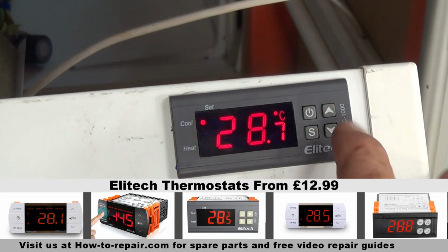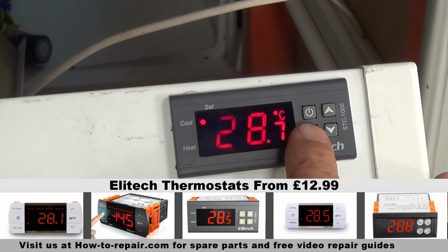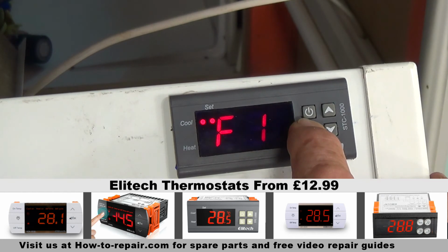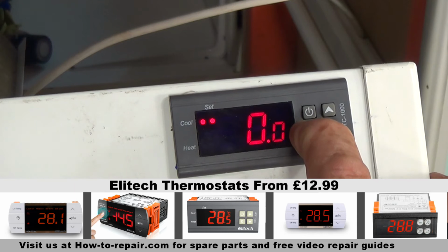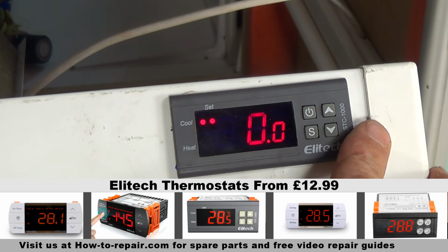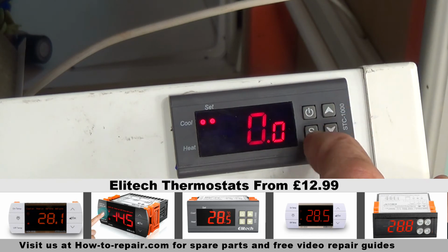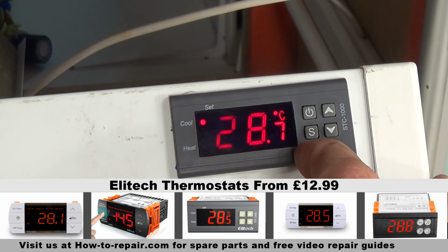That is now set. There is one more setting on this, which is F4, the calibration of the thermostat itself, or the sensor. So we just go into set, hold it down for 3 seconds, change it to F4, press set again, and as you can see it's set on 00, meaning that the temperature you're seeing on the screen is exactly what the temperature is on the probe inside the fridge. We're going to leave this exactly as it is. Now if you were using the heating mode for incubators or brewery equipment, whatever, you may want the delay on F2, the differential, to be different, and you may need the temperatures set up differently.